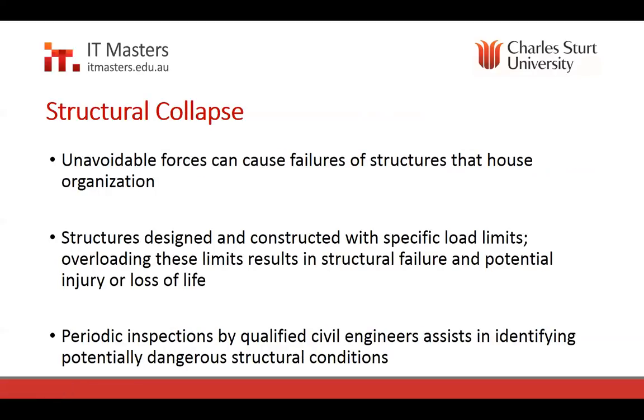Structural collapse, look, probably less of an issue unless you live in the Shaky Isles, so it's New Zealand for those who don't know, or somewhere along the San Andreas Fault, or somewhere in an earthquake-prone, volcano-prone area. But it is possible. It's something that needs to be considered. So one of the things I think is more important, and I can give an example of this too, unfortunately, is thinking about the load ratings of the flooring that you're putting your equipment on. So again, quite a few years ago now, there was a data center for a fairly large national carrier. Well, it's not the biggest, but certainly not the smallest. And they had a data center in Carlton that they just kept jamming more and more stuff into their cabinets, without really thinking about the loading of the floor, and the false floor collapsed.